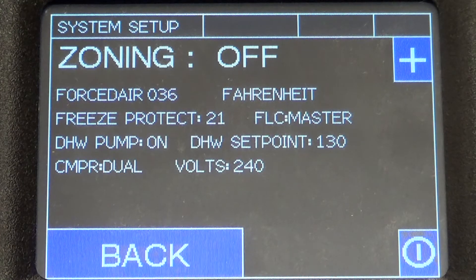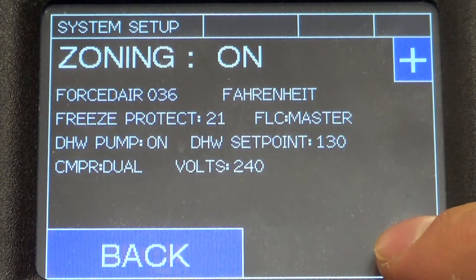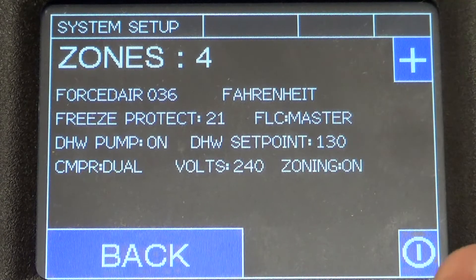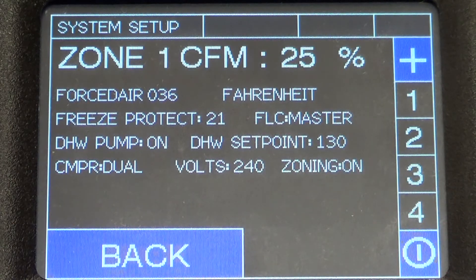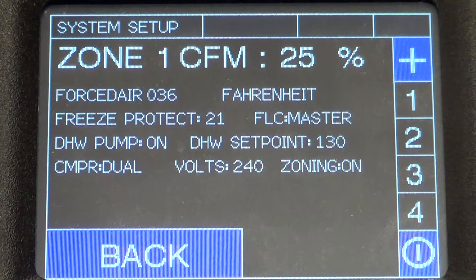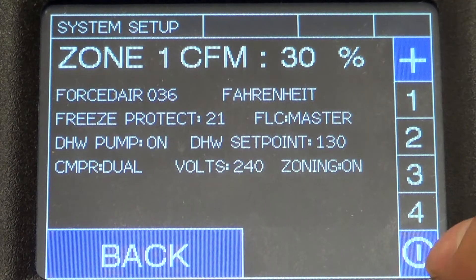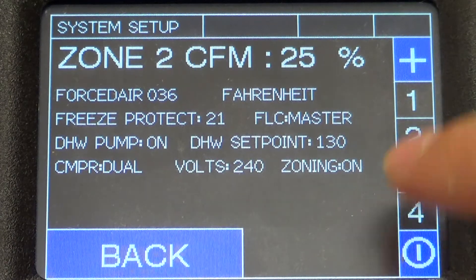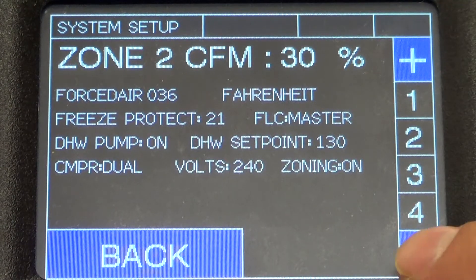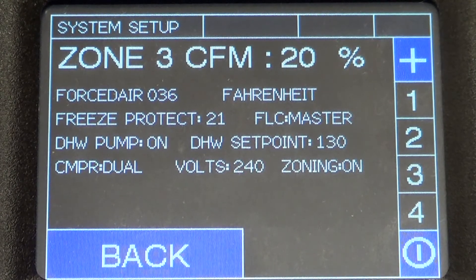The ORB also comes standard with control of up to four zones. Let's turn zoning on and go to four zones. The ORB allows you to select the percentage of airflow to each zone — it defaults to 25% for all four. Maybe your main level is 30%, zone two the upstairs is 30%, and zone three the basement is 20%.